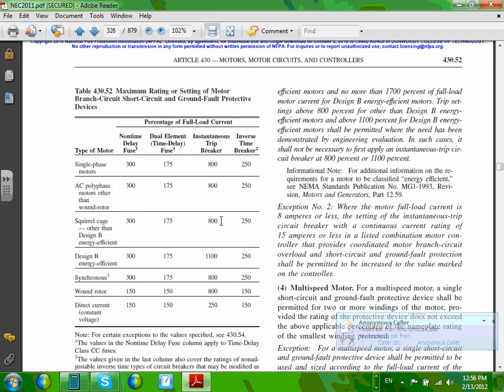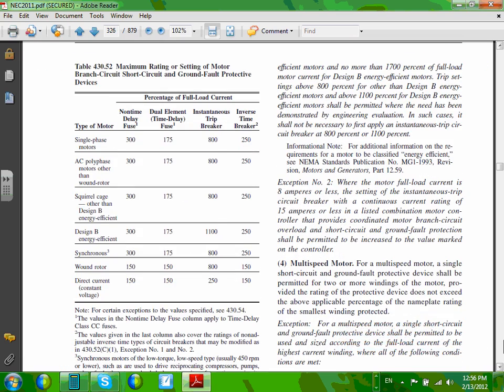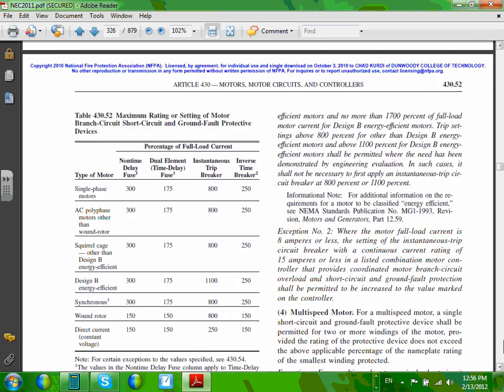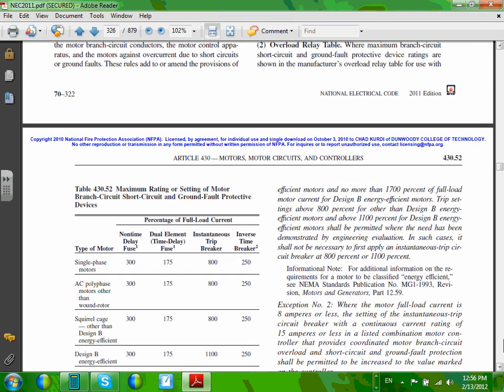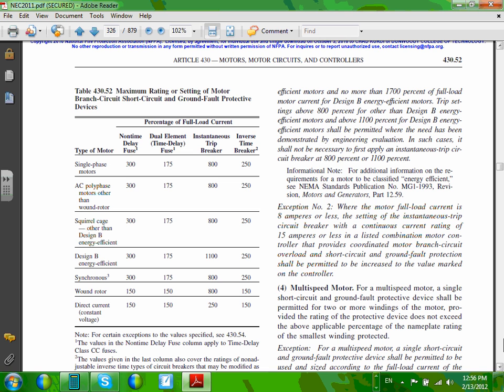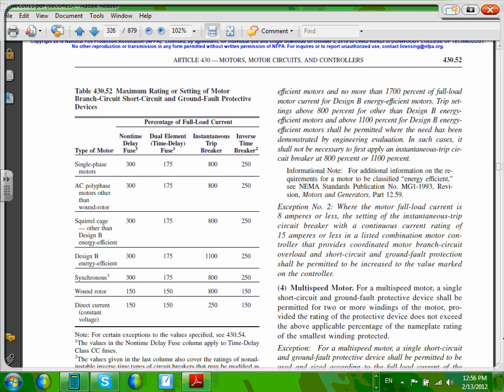Okay, give me a second here. Right here. This is the table that you need right here. It's page, for you, it will be page 323. Are you guys there? 323. Now this applies for all motors. Your motor, guys, is single phase. You are most likely induction motor. If you're using non-time delay fuse, your multiplier is 300. If it's dual time, 175. 99% in this project, we're going to be right here.